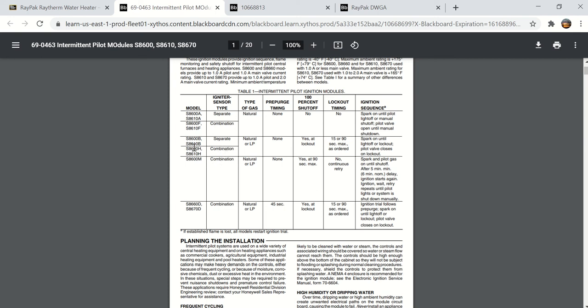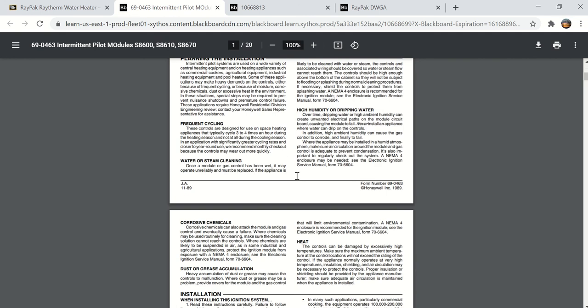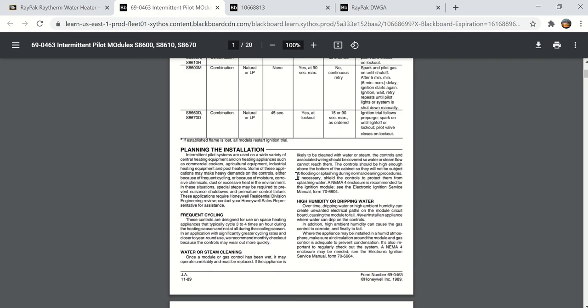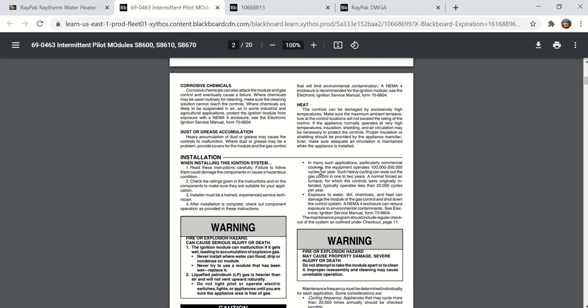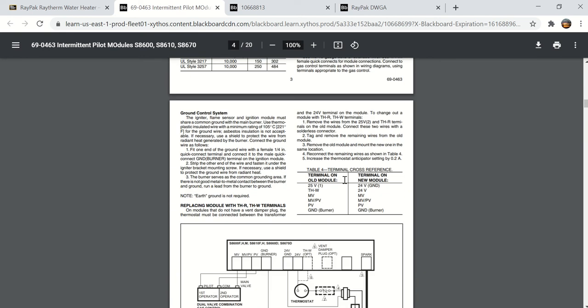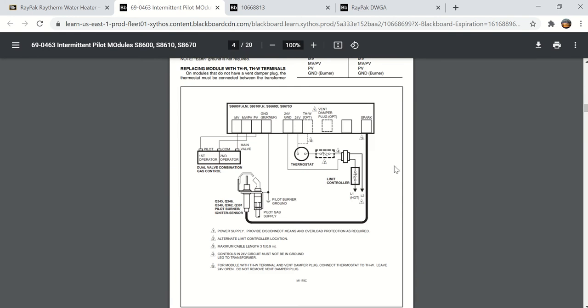So the S8600H is probably the most common one you see here. No pre-purge, doesn't have a blower. It's an atmospheric burner, so it doesn't have any of that. It will spark until it lights or lock out. Pilot valve closes on lockout, so you don't have pilot gas. But the way that you reset these flame safeguards when they fail is to cycle power. That's the only way to do that.